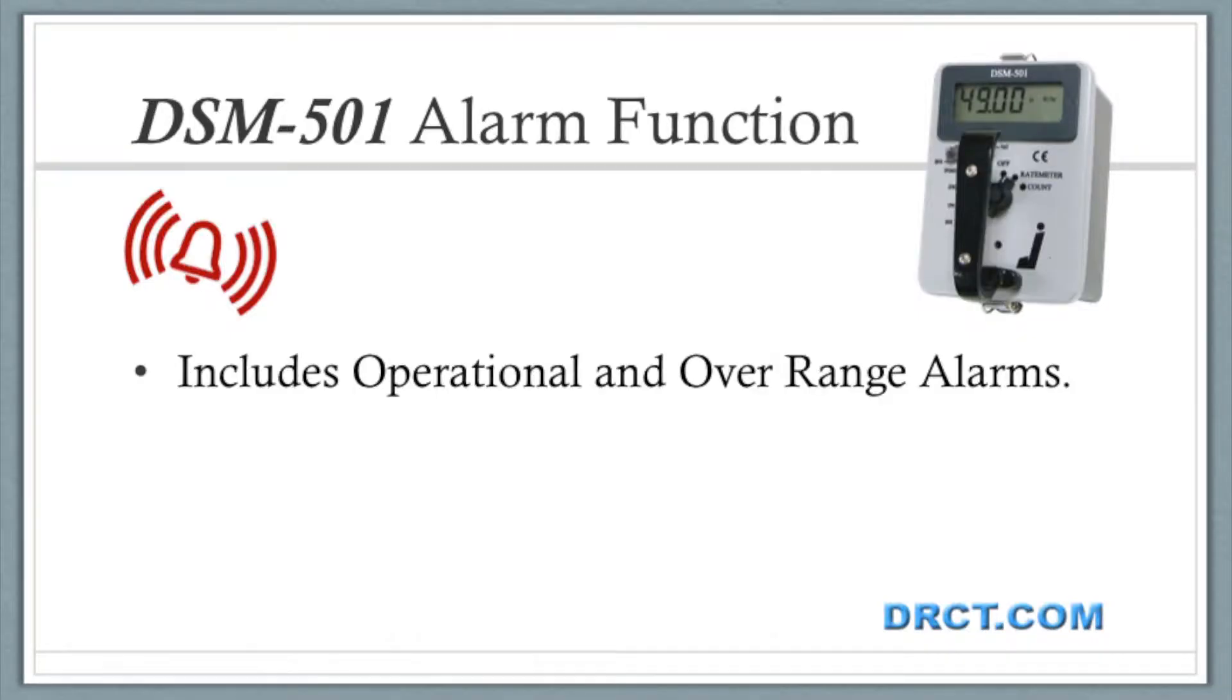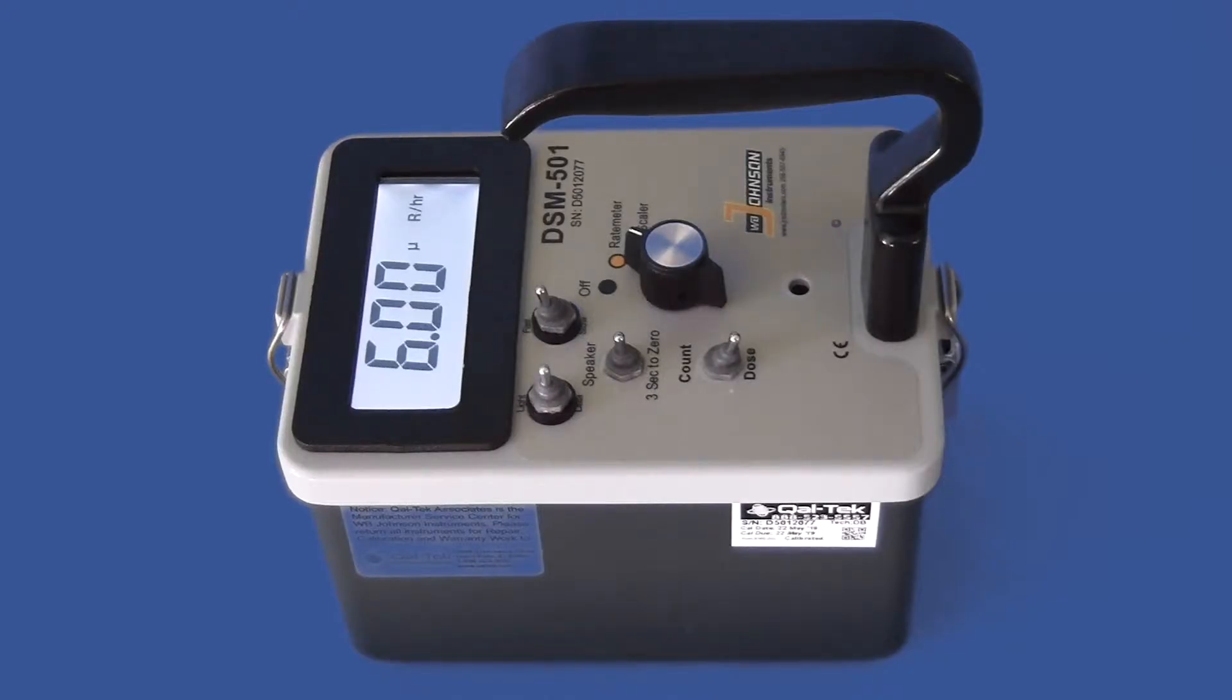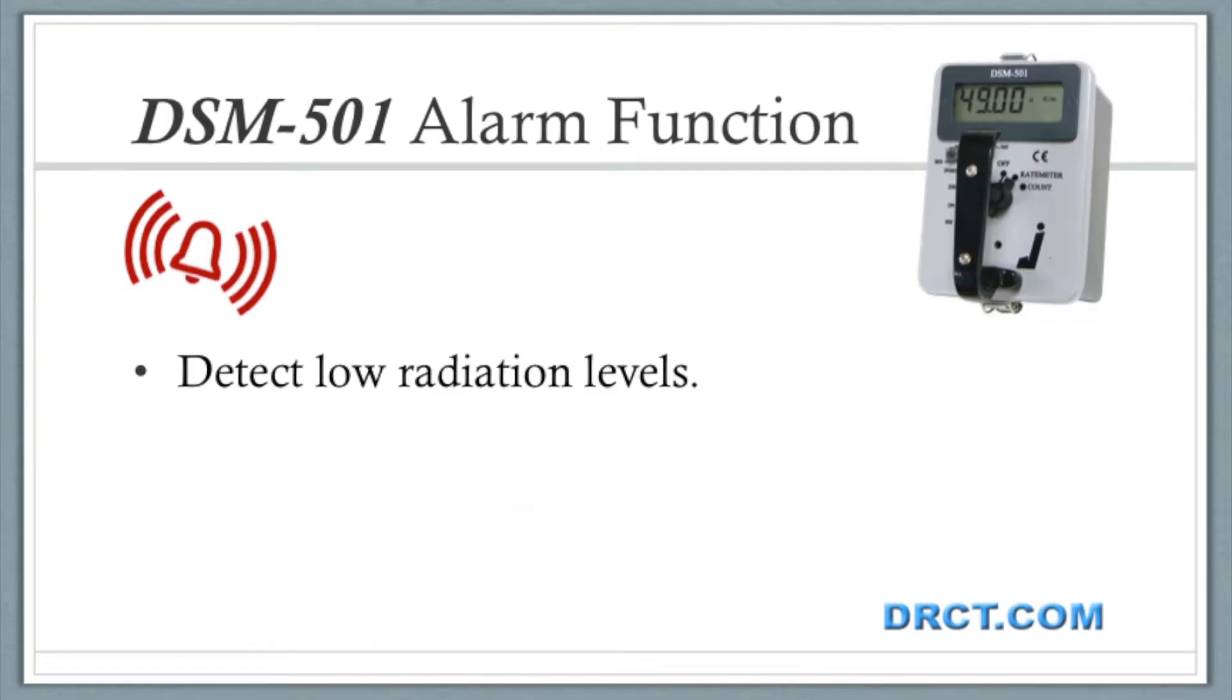The DSM-501 includes both operational and overrange alarms. Both are user set. For the operational alarm set point, the rule of thumb is to set it at twice the background. Our background is about 7 microroentgen per hour. For our demonstration, we will set it at a little over, at 20 microroentgen per hour. This helps us locate low-level radiation while avoiding excess noise.